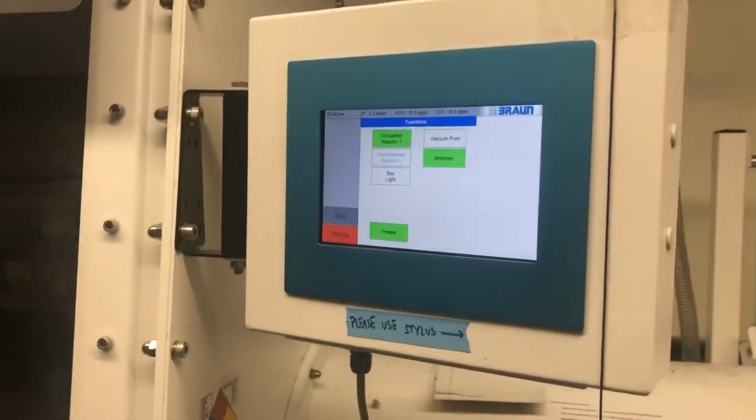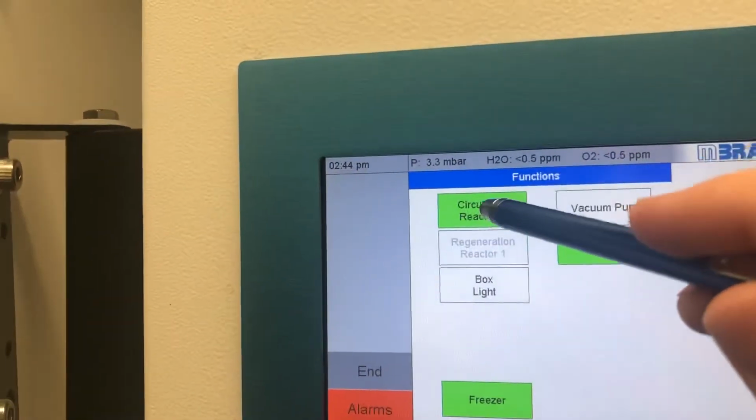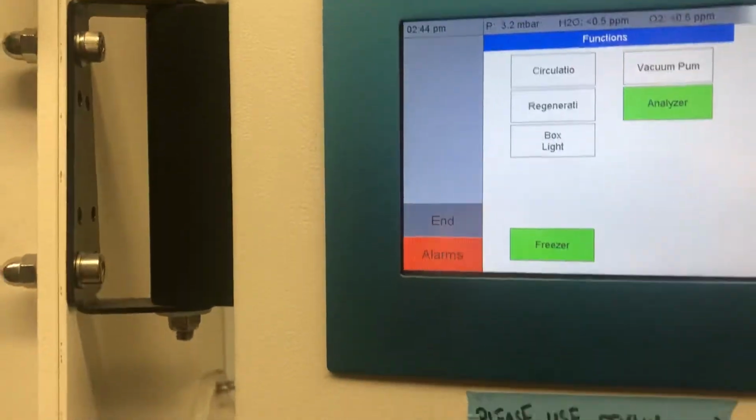Okay, so this is the purging video. This is for those of you who will be handling liquids. While you're handling a liquid, your circulation should be off. When you push it off, you hear this beautiful noise. It just shuts off, right? So now that means that the air is stagnant and is not circulating around in here anymore.